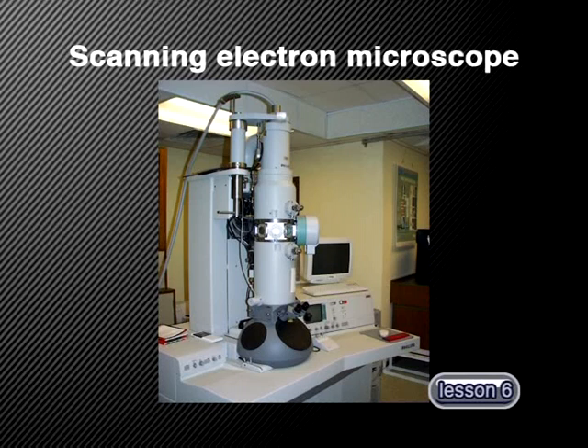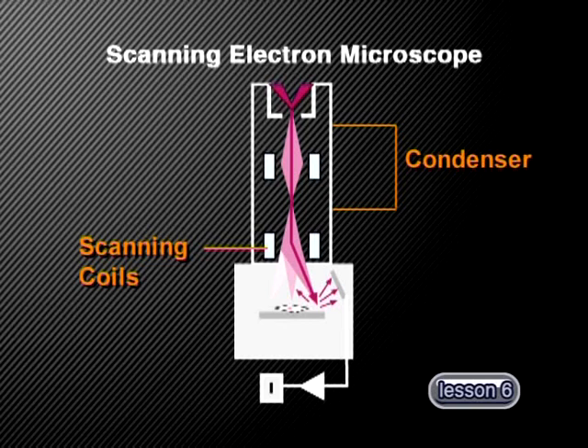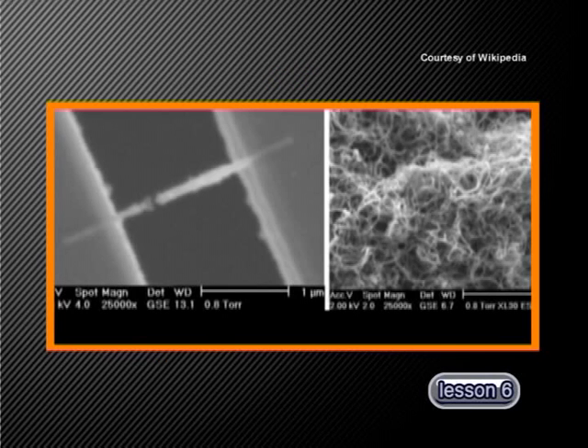A scanning electron microscope works in much the same way as a transmission electron microscope until the electrons reach the sample. Here, a set of scanning coils moves the beam of electrons back and forth across the sample. As the electrons hit each spot on the sample, secondary electrons are knocked off from the sample surface. A detector then counts these secondary electrons and sends signals to an amplifier, which then builds up the final image based on the number of electrons emitted from each spot on the sample. The image formed is similar to the one we get from a transmission electron microscope, but gives a better 3D view of the structure. Let's visit Mintec, where they regularly use different scanning electron microscopes.